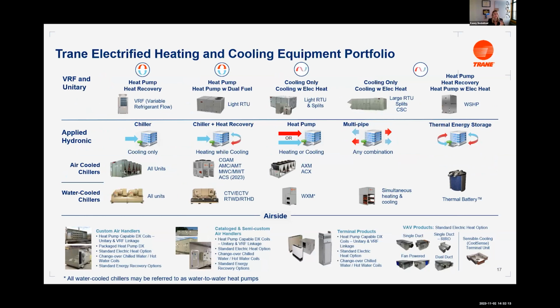This slide goes into a little bit more detail on the types of equipment available, but what I want to point out here is the applied hydronic line. You could have your traditional chiller system where it's cooling only. And Colin talked about this a little bit, so in order to leave time, I will try to go through this very quickly. But then you could have a chiller that utilizes heat recovery, so you're heating while you're cooling. The next step beyond that would be heat pump, so you're heating or cooling, and you could be controlling to those temperatures. The next one would be multi-pipe, which is where you are heating and cooling all simultaneously. And then finally is thermal energy storage. And that's what I wanted to talk about when we talk about cool new solutions available.